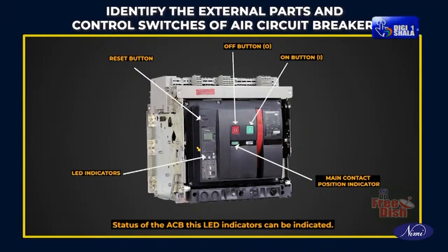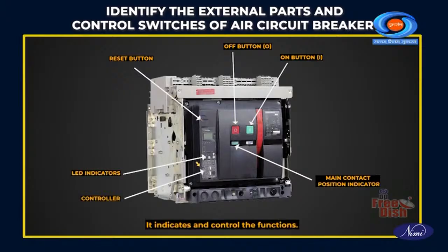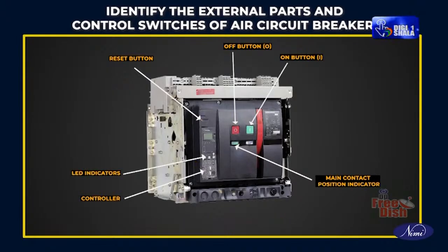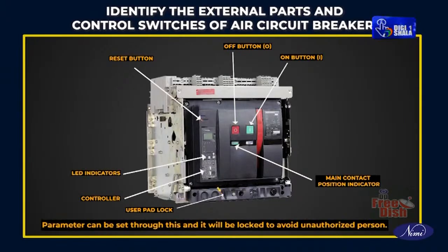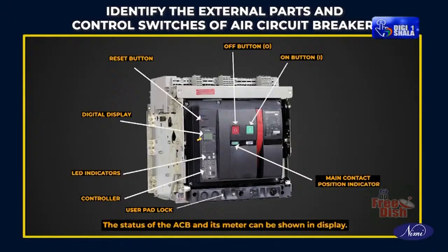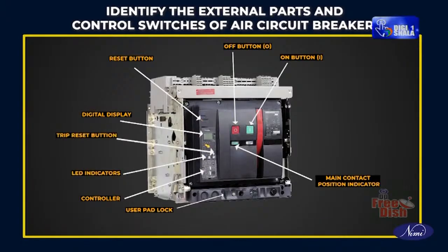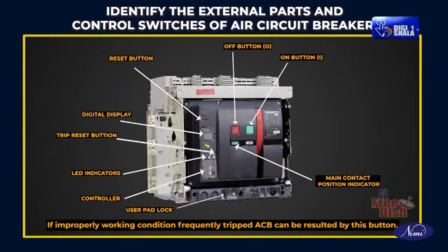LED indicators: status of the ACB. These LED indicators can indicate the status. Controller: it indicates and controls the functions. User padlock: parameters can be set through this, and it will be locked to avoid unauthorized persons. Digital display: the status of the ACB and its meter readings can be shown in the display. Trip reset button: if the ACB is improperly working and frequently tripping, it can be reset by this button.